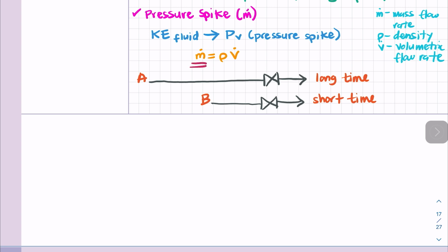So there is a direct relationship between mass flow rate and pressure spike in a piping system, right? The mass flow rate refers to the amount of liquid or fluid that passes through a given point in the piping system per unit time. That's flow rate. While a pressure spike refers to a sudden and brief increase in the pressure. So a brief increase in pressure, it can be at a certain point.